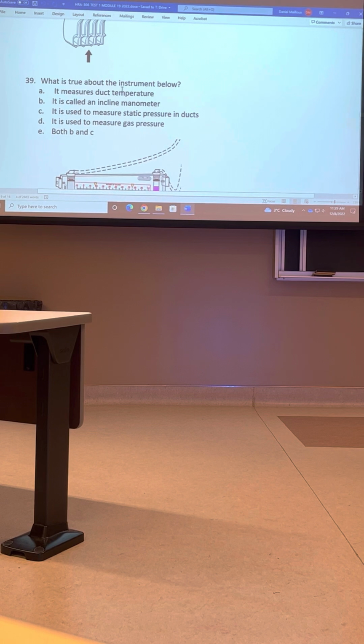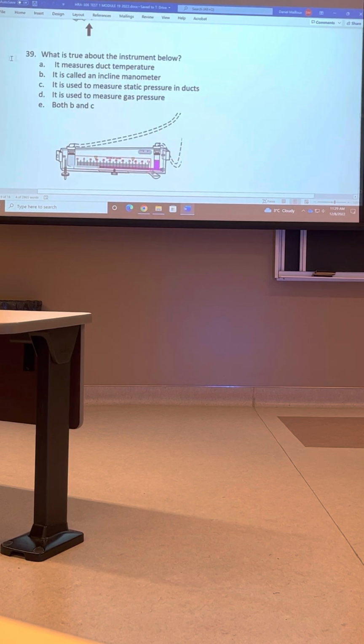What is true about the instrument below? Both B and C. Okay, this is an incline manometer. You have to set it up and level it, and it's on a slope. It's used to measure small amounts of pressure, usually for static pressure in ducts.